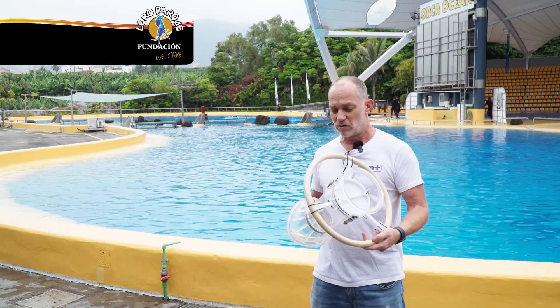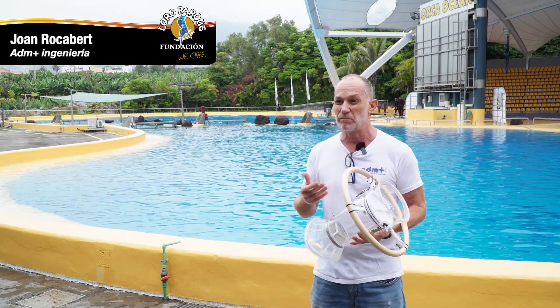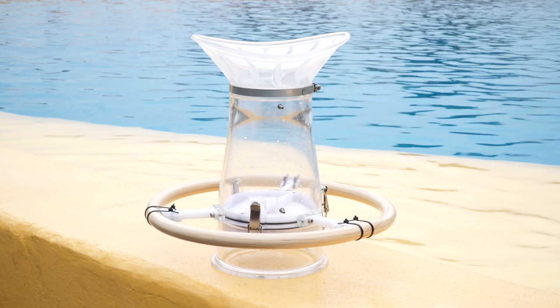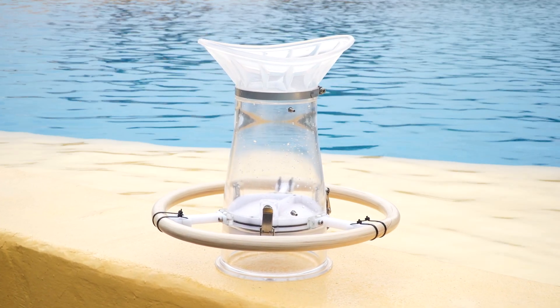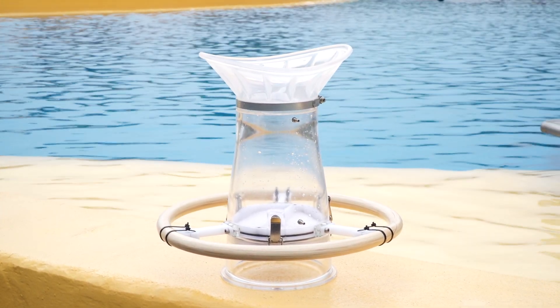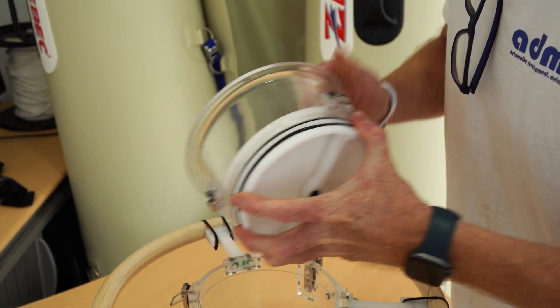It was necessary to develop a flowmeter similar to what we developed for dolphins, but of a larger size for animals of large size and lung capacity. This basically works like a venturi tube. First, you have the block that is coupled with the animal, creating a channel that is completely sealed, which takes the inspiration and expiration of air through the upper part.